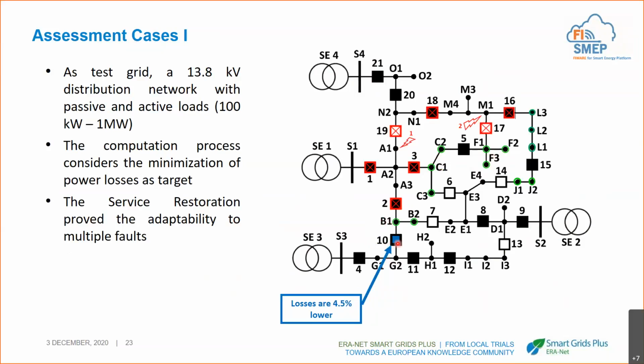In case we have closed this switch and a second fault occurs, we have again to isolate by opening the neighbor switches. We have an additional set of loads that are now disconnected. And there is only one way to reconnect these loads, which is via closing this switch, because it's the only one that is connected to these loads. Now, the last group of loads that need to be reconnected are these ones. And they can only be reconnected by the switch 6. In this way, we reach the limit of the maximum current that can flow, and so we are in an emergency condition that can last only a limited amount of hours.